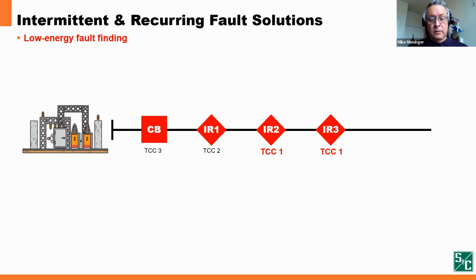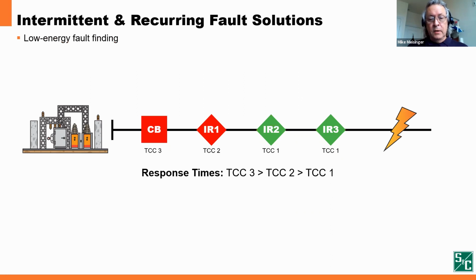And the next click, please, Clever. So as before, TCC3 at the circuit breaker is slower than TCC2 for IR1, but IR2 and IR3 have intentionally been set to the same time current characteristic. Next click, please. So when a fault occurs, we have intentionally expected that both IR2 and IR3 will respond to the fault because they're set identically. Next click. So IR2 now initiates its low energy fault testing, and because IR3 is open, it detects no fault. Click, and closes. IR3 now has system voltage and it initiates its low energy testing.